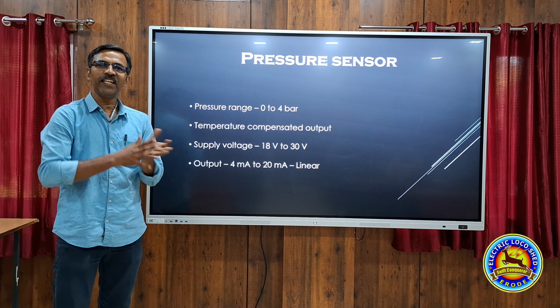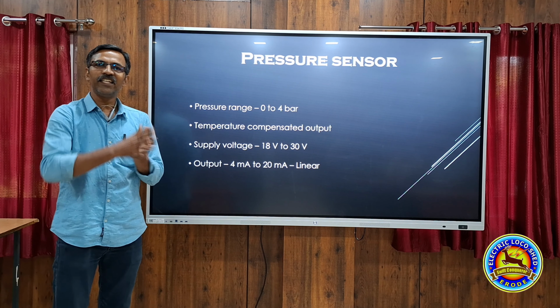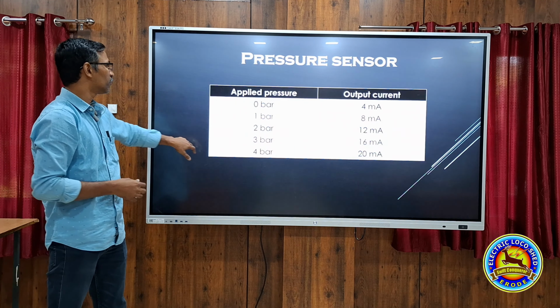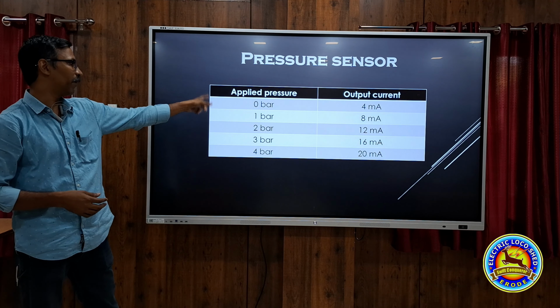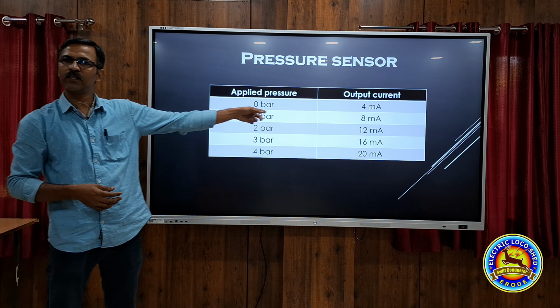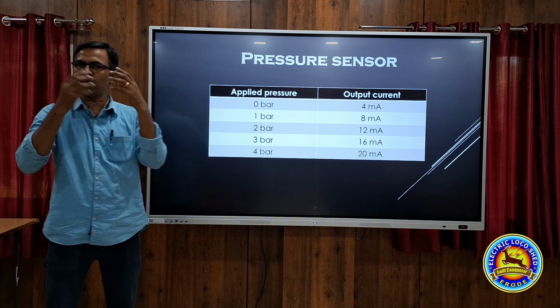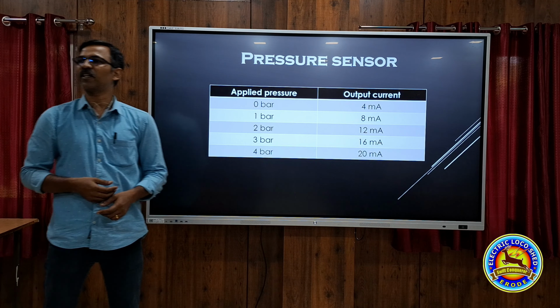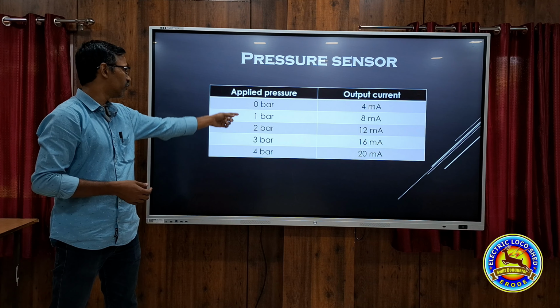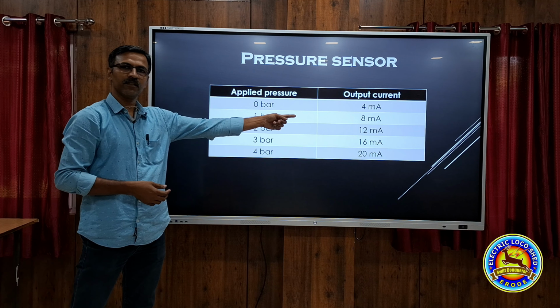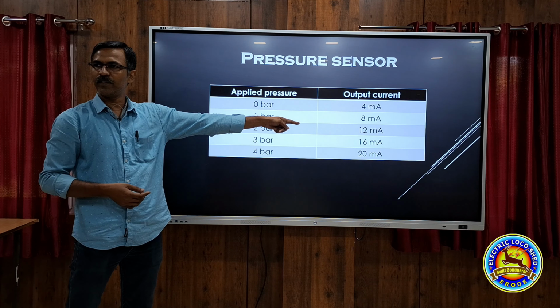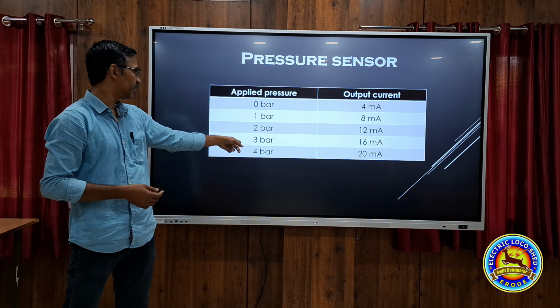It is exactly linear to the pressure. As the pressure increases, the current increases. This is the applied pressure and the output current that we get from the sensor. If the pressure is 0, we will get 4 milliamperes. As the pressure increases to 1 bar, 2 bar, 3 bar, the output current also increases. At 1 bar, we get 8 milliamperes; at 2 bar, 12 milliamperes; at 3 bar, 16; and at 4 bar, 20 milliamperes. That's the maximum limit.